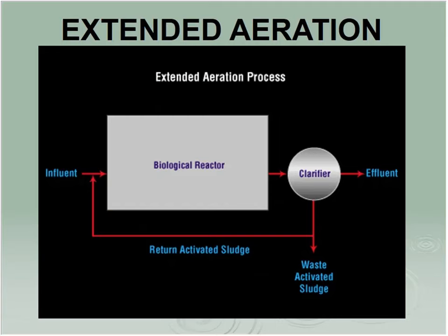Now, extended aeration. Extended aeration is the process that actually works and relies on that endogenous phase of the organisms. And it says extended air, it's not kidding around. Instead of retention times of 5 to 15 days, we're talking 20 to 30 days. These are very common in seasonal towns, beach towns, ski towns, that sort of thing. We've got a big population for a while, and then everybody goes away.